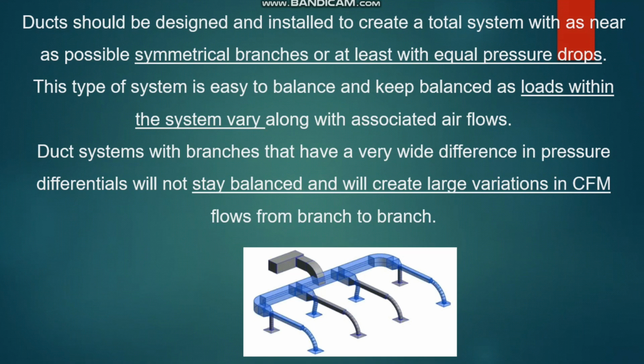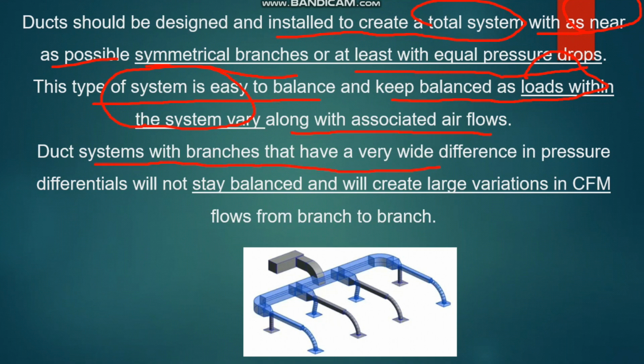So here the branches are not equally distributed, and sometimes we cannot avoid this type of thing on site. So the answer here is, ducts should be designed and installed to create a total system that is as symmetrical as possible. I mean, you have to try to make the branches symmetrical, or at least with equal pressure drops. This type of system is easy to balance and keep balanced when the load within the system varies. Because the room load is varying continuously, we can easily balance the system and also the associated air flows. A duct system with branches that have a very wide difference in pressure differential will not stay balanced and will create large variation in CFM from branch to branch.